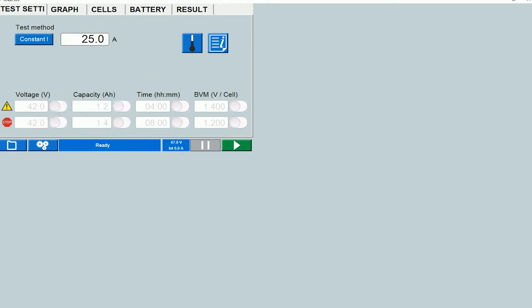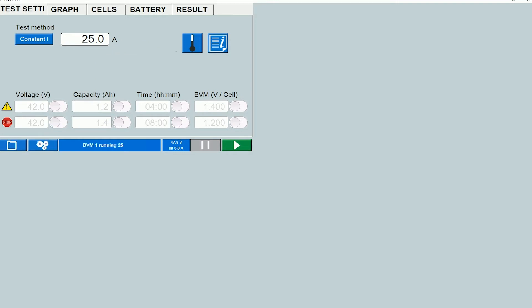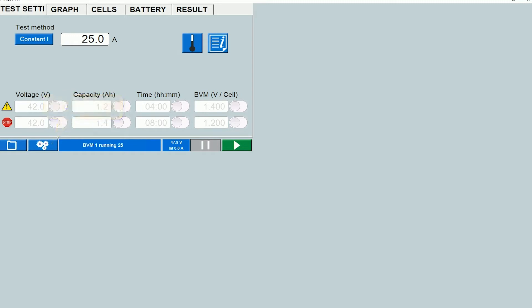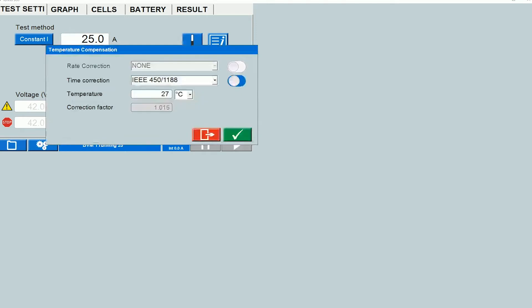One of the most important steps is to make sure that you enter the temperature correction factor. The temperature correction factor can be set by accessing this icon. If this icon is grayed out then that means that the temperature compensation is disabled. It can be enabled by accessing the configuration screen over here. To set the temperature correction factor you would click on this and the window that comes up shows you the two options for capacity calculation, rate adjustment method, the time adjust method. In this case the time adjusted method is selected and you can see that the IEEE standards are selected.